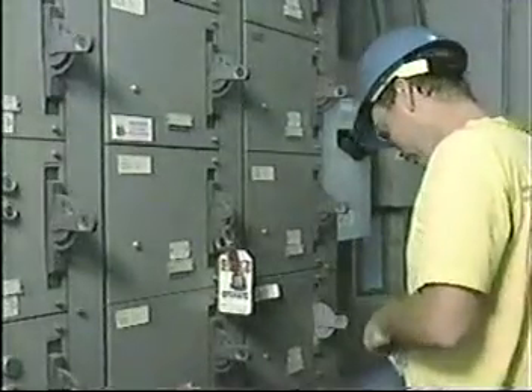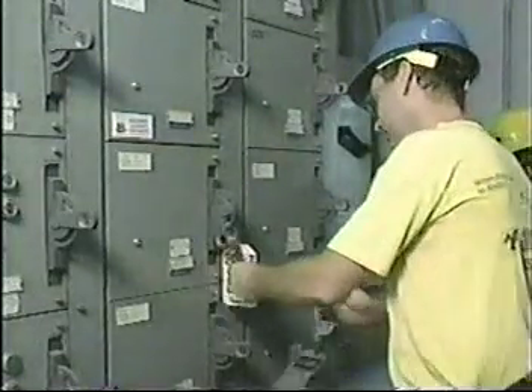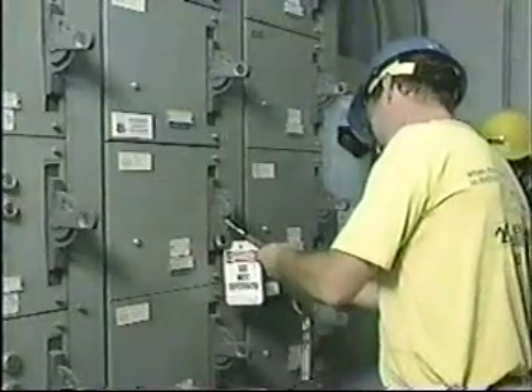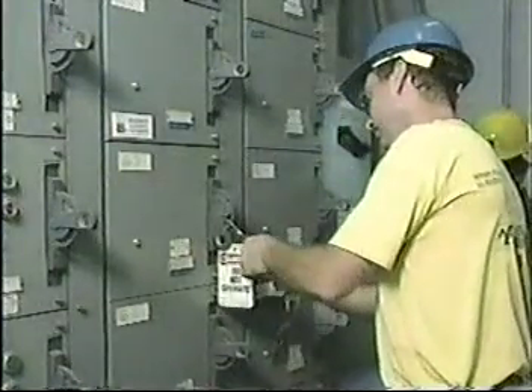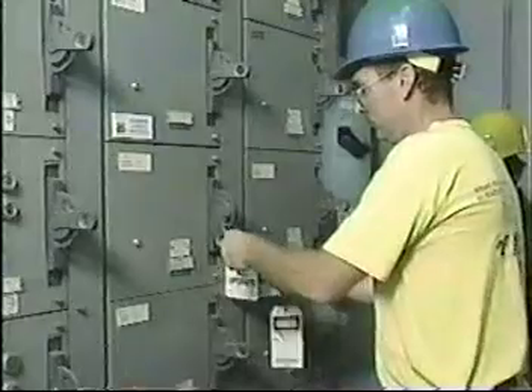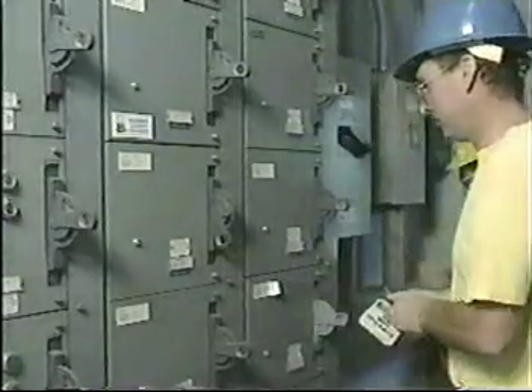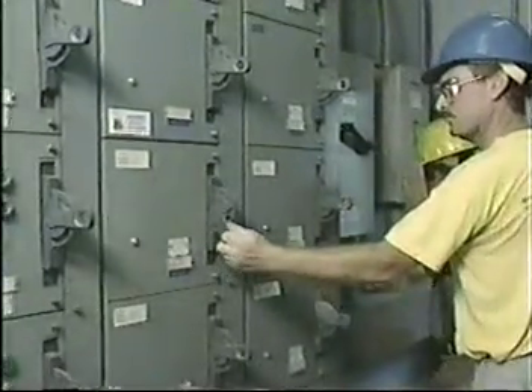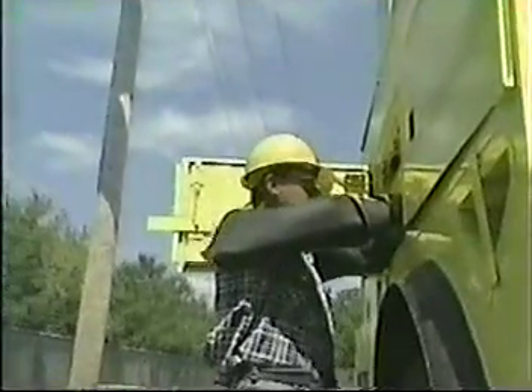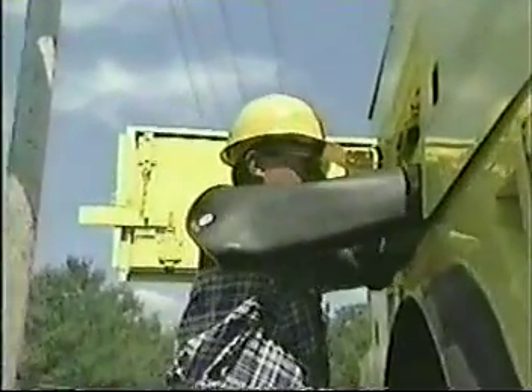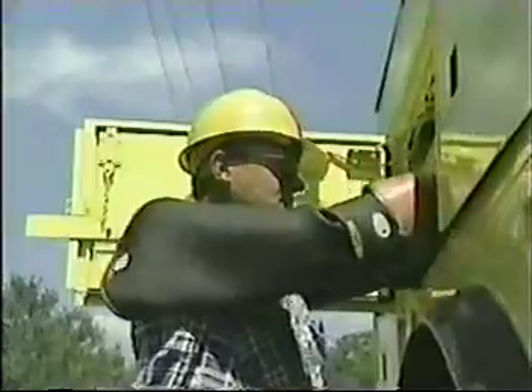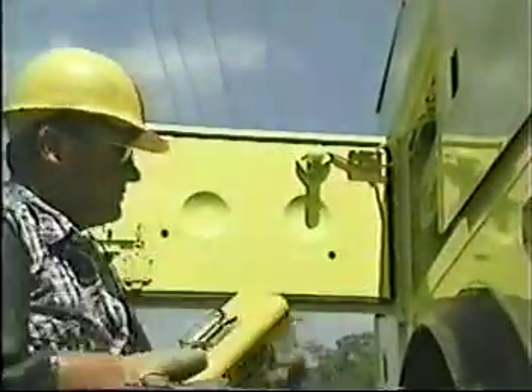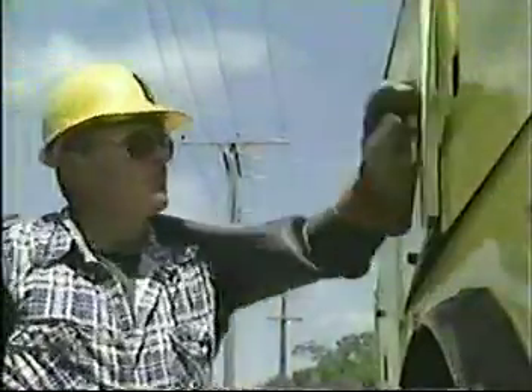Whenever possible, open or close circuits with the panel door closed, using external handles or relay controls. If it is necessary to open it to reset a circuit breaker, stand to one side to minimize the possibility of an arcing injury. Protective clothing should be worn when the voltage or amperage is high, especially if the circuits include electric motors or transformers.